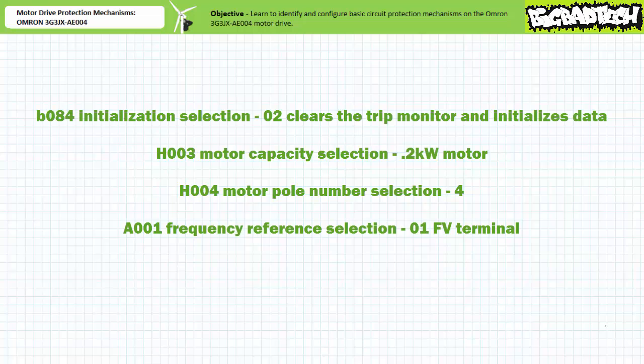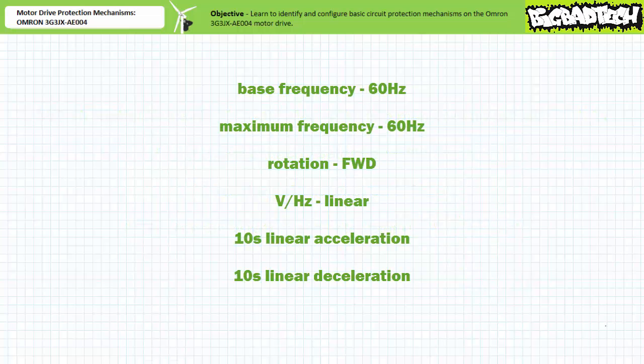Finally, we'll program the drive to recognize an external speed potentiometer input using extended function parameter A001. This start state establishes a 60 Hz base frequency, a 60 Hz maximum frequency, forward default rotation, a linear volts per hertz ratio, a 10 second linear acceleration time, and a 10 second linear deceleration time, among other properties. This motor drive is now ready for today's activities.